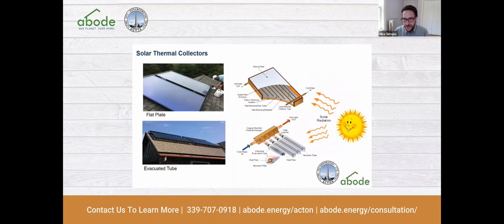One way to do it is through solar hot water systems, also called solar thermal. There are two types: flat plate collectors and evacuated tubes. If you have plenty of room, because you haven't already gone solar PV, flat plate collectors are a great way to go. They produce a little less energy per square foot, but there's probably less issues with maintenance, and they literally last like 30 years. With either of these systems, you're probably looking at displacing 60 to 70% of your annual energy use that goes into domestic hot water.